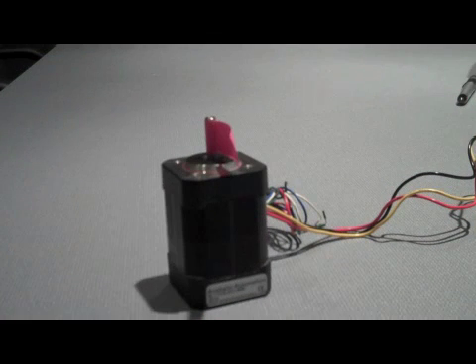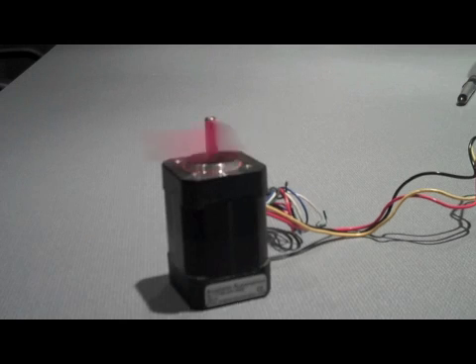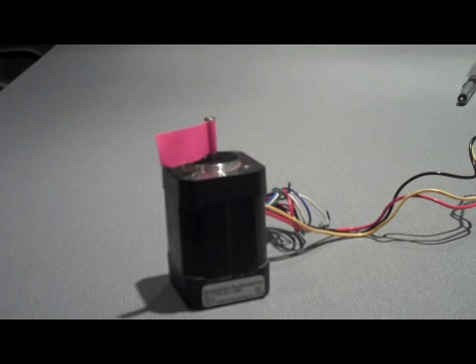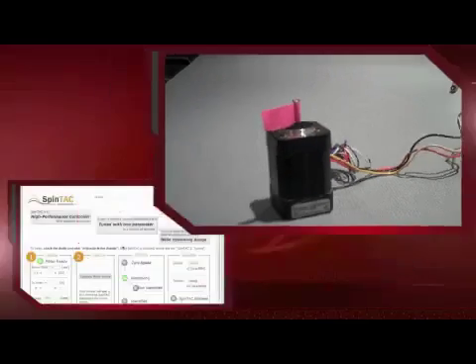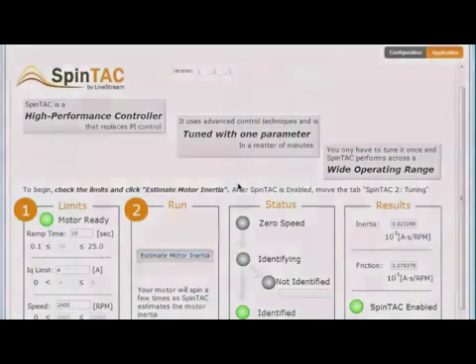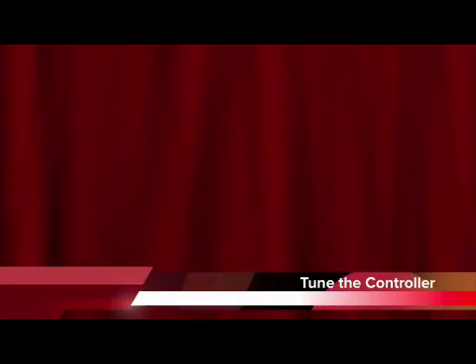The system will accelerate and decelerate the motor to get a picture of how much mass is connected to the motor shaft. The inertia value is used by the controller to determine how strongly it needs to compensate for disturbances in the system. The process is now complete. Now that we've identified the system inertia, we can tune the controller.